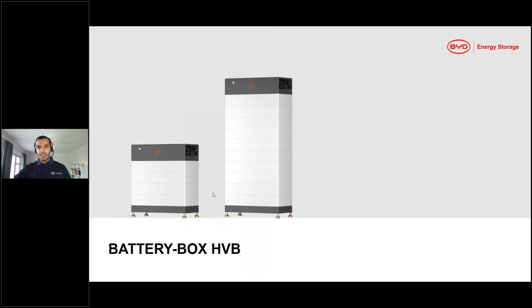First, let's have a look at the different capacity options possible with the HVB. With the HVB, it's possible to start with 2 modules in one tower, giving you a capacity of round about 6 kilowatt hours, and it's possible to have up to 10 modules in one tower, giving you a capacity of up to 30 kilowatt hours. So from 6 kilowatt hours up to 30 kilowatt hours, you're able to design capacities of different ranges, and every additional module gives you an additional 3 kilowatt hours of capacity, in 3 kilowatt hour steps.